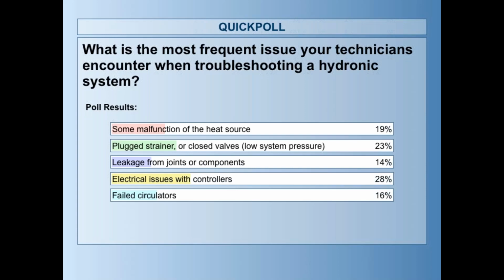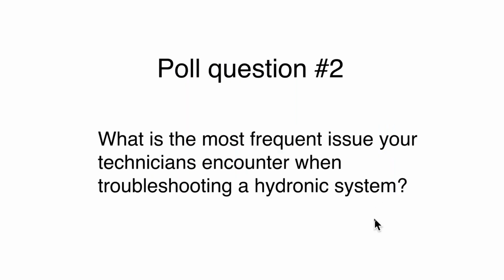Electrical issues. Yeah. Today, as we put more and more electronic controls into systems, we're likely to see that more, especially if the electrical system in the building doesn't have some type of surge suppression in it. I would recommend that certainly today in any hydronic system with electronic controls, some kind of surge suppression in the system to prevent a brownout or a nearby lightning strike or whatever could cause a voltage transient from damaging those controllers. Okay. Send it back over.